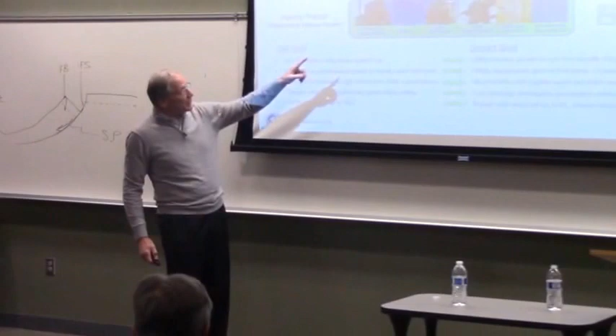For instance, voltage control: if I control voltage, I directly control load, since voltage is directly proportional to load. So the way we can manage load is we can raise and lower the voltage. When I control reactive power, I can control losses, I can reduce losses. There's a very strong business case today with voltage and reactive power, and we're integrating those together today to do integrated volt-var control. That's why it's shaded halfway. On the left side, we've been doing voltage control by itself for decades, and reactive power control by itself for decades, but now we're integrating them together.